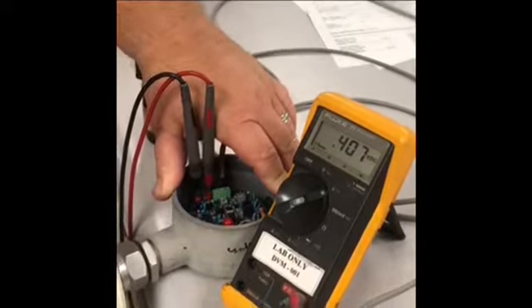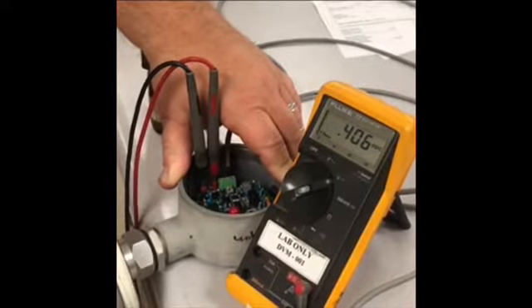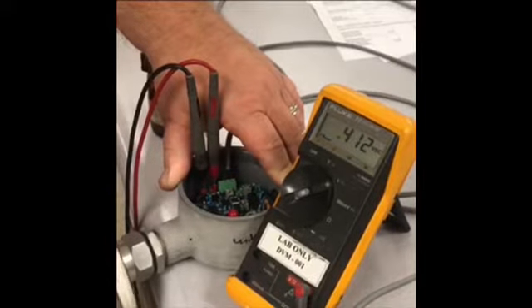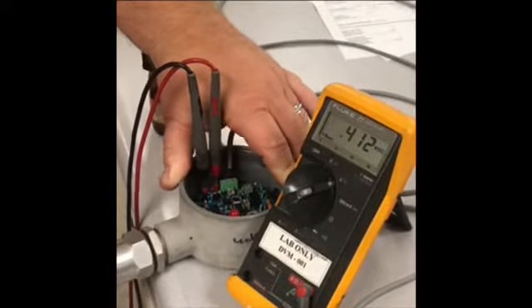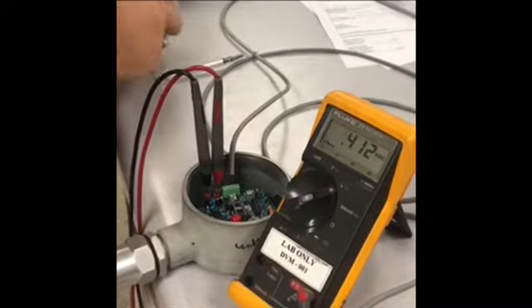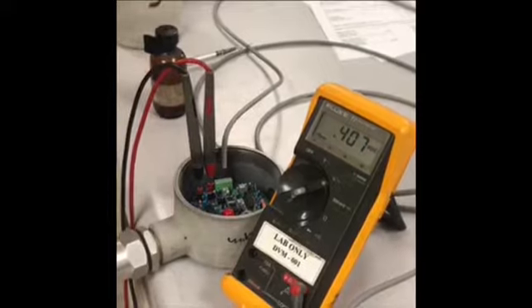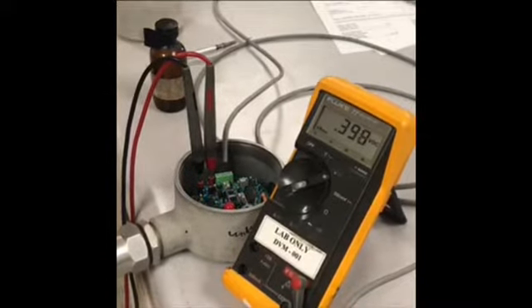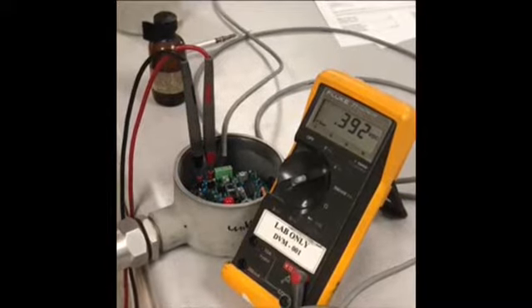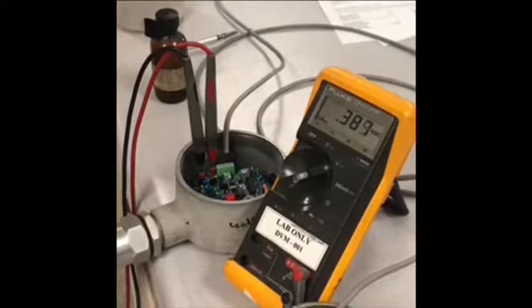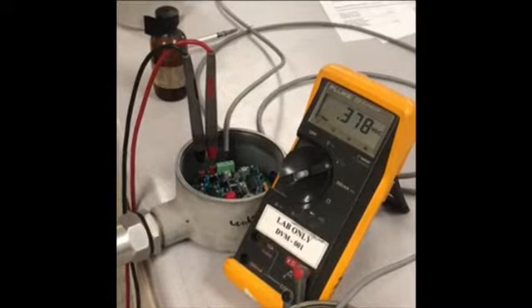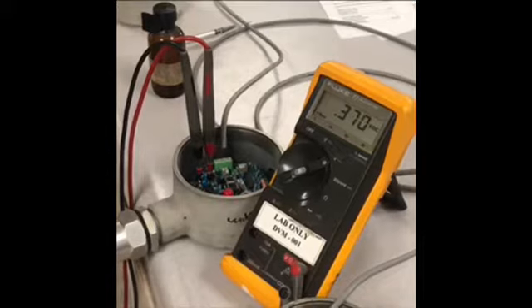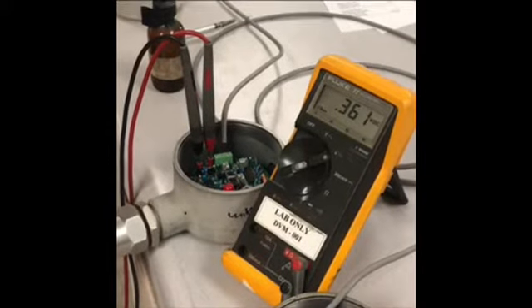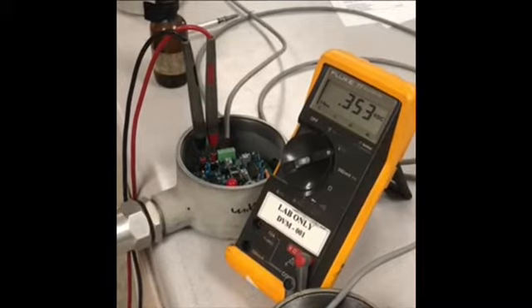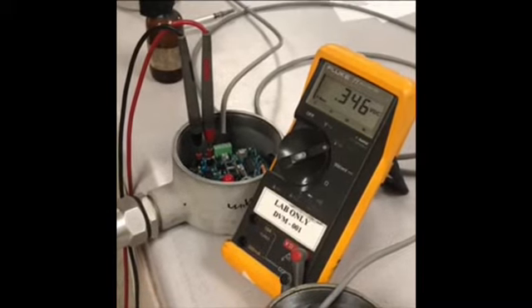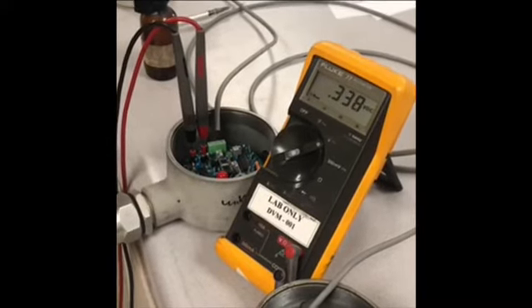I'm going to go ahead and take this off just for this training video. I would still let it tick up like that and adjust it down. It could take a couple of minutes. But once you remove the gas, you should be able to see the reading begin to come down. The reading will continue to come down like that. It could take up to 15 minutes for it to read 0 again. 0 output would be 0.1 volts like we started with. As you can see, it comes down fairly slow, especially with ammonia at this concentration. But that is how you calibrate a sensor. You would do that to each one of these sensors, just like that.